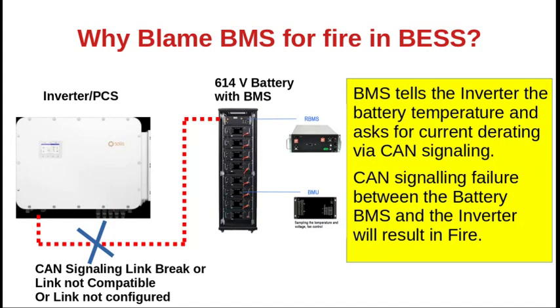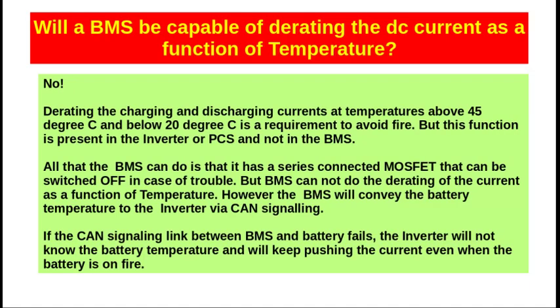How? Actually, the BMS tells the inverter the battery temperature and asks for current derating via the CAN signaling link. But if there is a CAN signaling failure, it can result in fire. Will a BMS be capable of derating the DC current as a function of the temperature? Unfortunately, the answer is no. All it can do may be to switch off the DC current in the BMS PCB in case of high temperature, but it cannot do the continuous derating function. The derating function of the current is in the inverter mainly. So only the inverter is the source for controlling the charging and discharging current of the BESS and not the BMS.